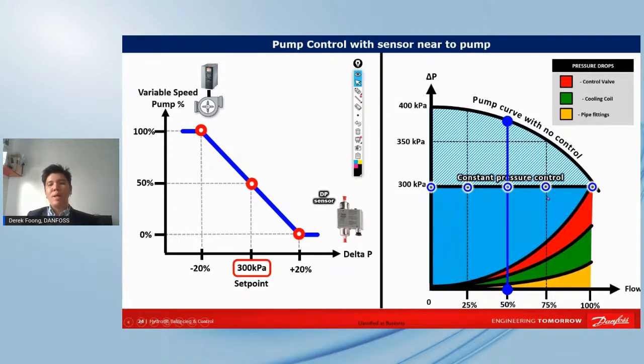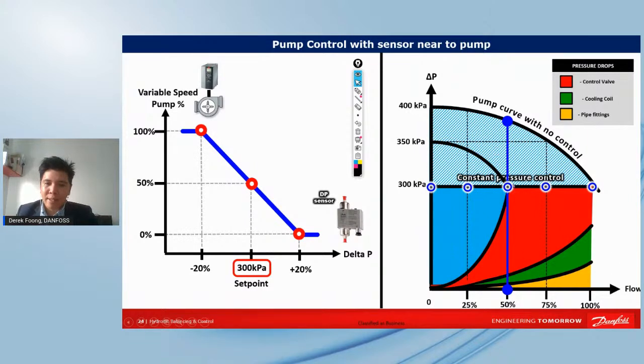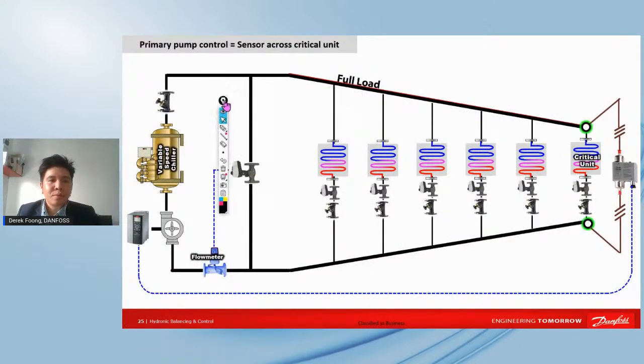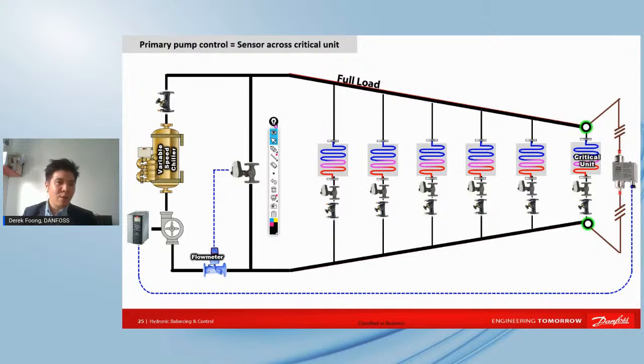So, okay. Now what happens if, let's say, some control valve closes? Then the control valve pressure doesn't actually go up to this area. So there will be a new pump curve also when you have constant pressure control. Instead of operating this much, the pump curve will become smaller together with the system curve. It moves. All right. So that is what we conclude on the pump's constant pressure control dynamics.